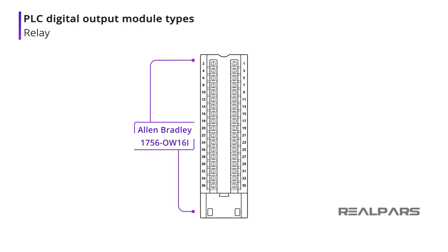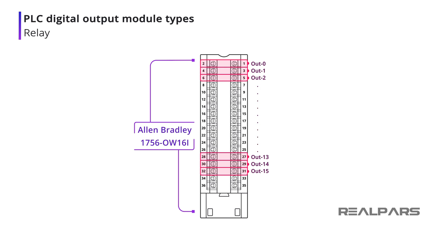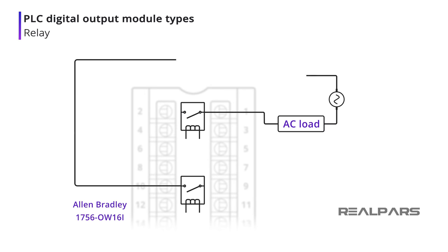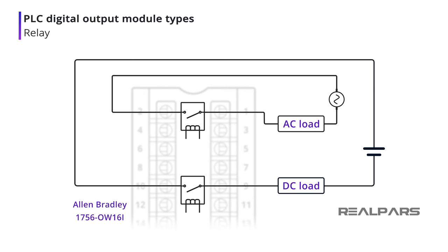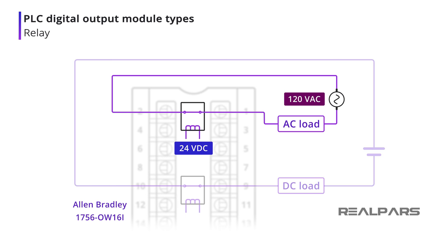Let's look at an example of an industrial PLC relay output module. The Allen-Bradley 1756 OW16I has 16 individual relay outputs. We can use one output to operate an AC load and another output to operate a DC load, as relay contacts are voltage independent. That's one advantage of relay type as solid-state type output modules are not voltage independent.